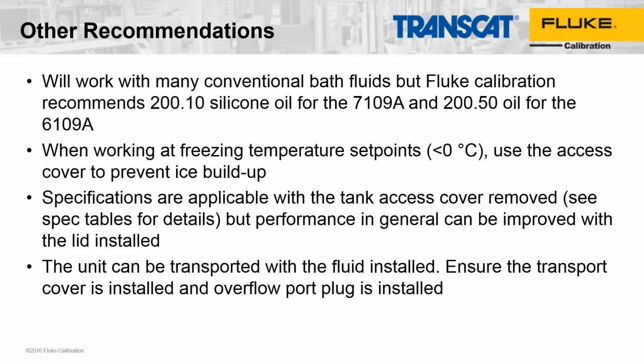If I remember correctly, there are some lids with some holes machined into them to accommodate probes with longer sheath lengths that can go through the lid and into the fluid to help fight this type of issue. The specifications are applicable with the access cover or the lid removed, but there are some details in the spec table where, in a couple of situations, there may be an addition that has to be made without using the tank cover or the access cover.